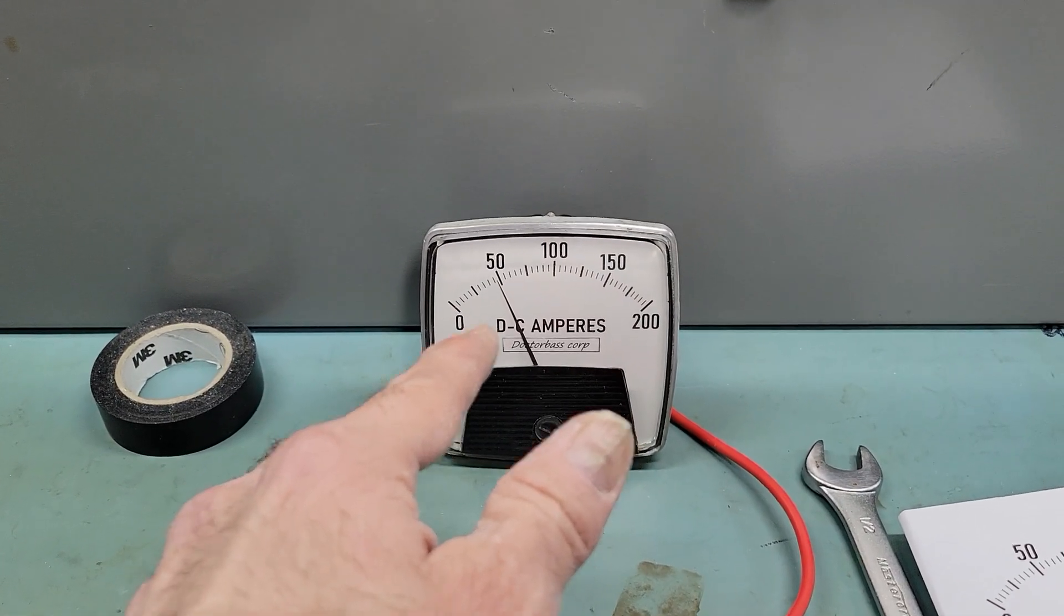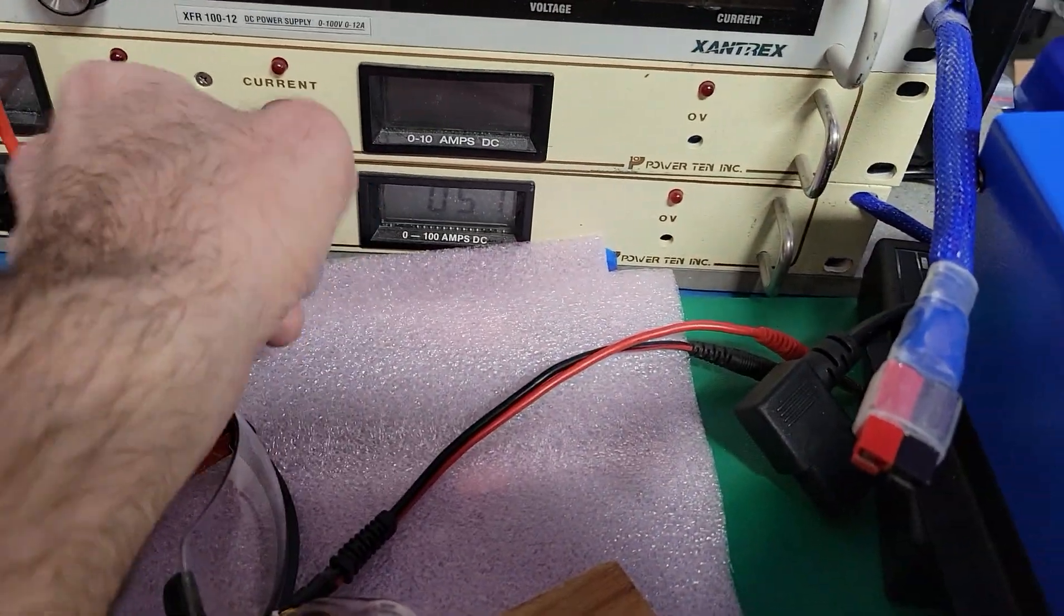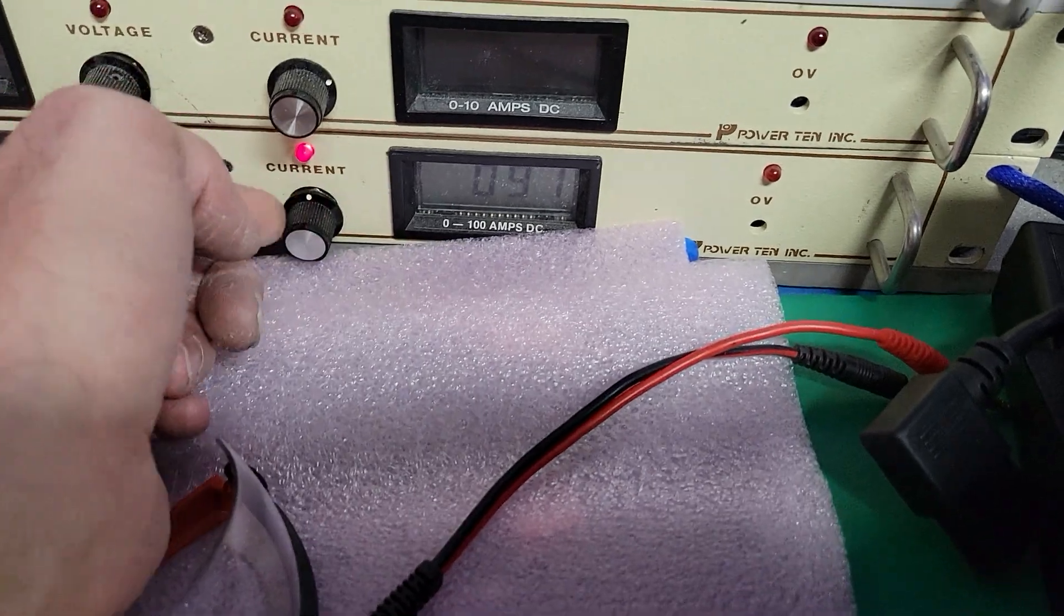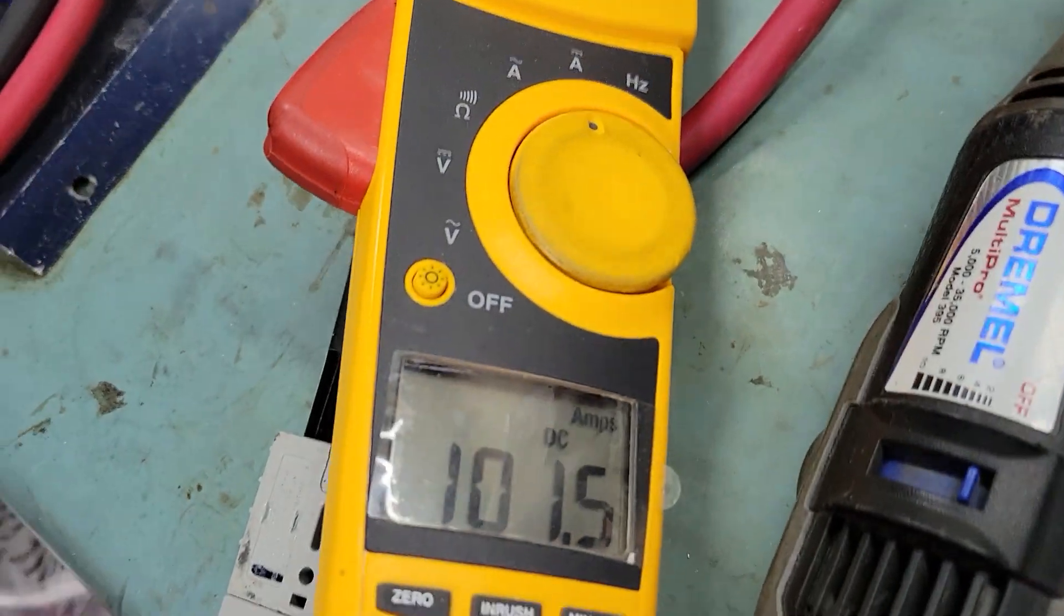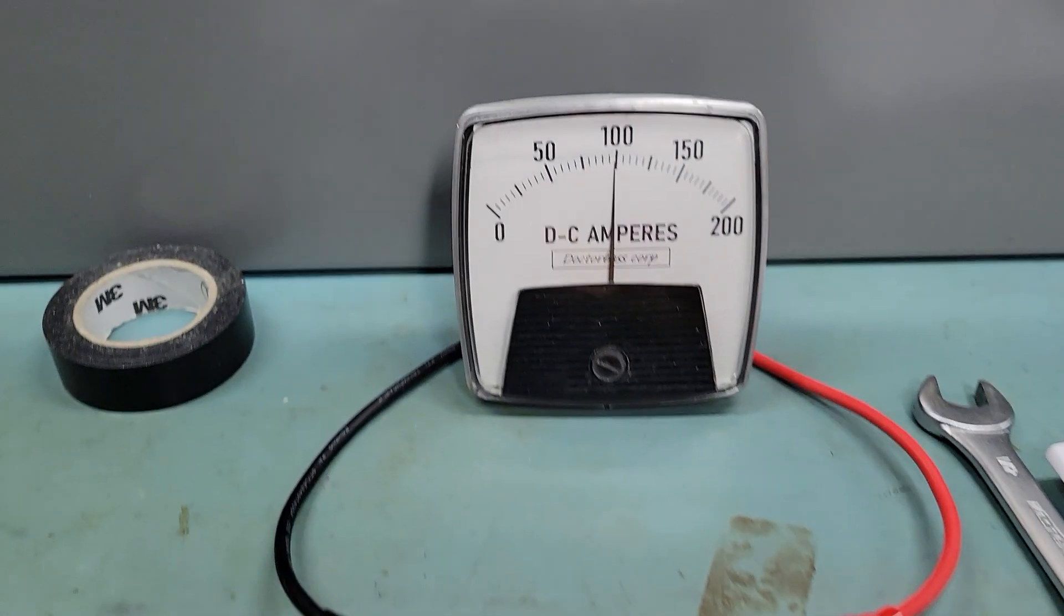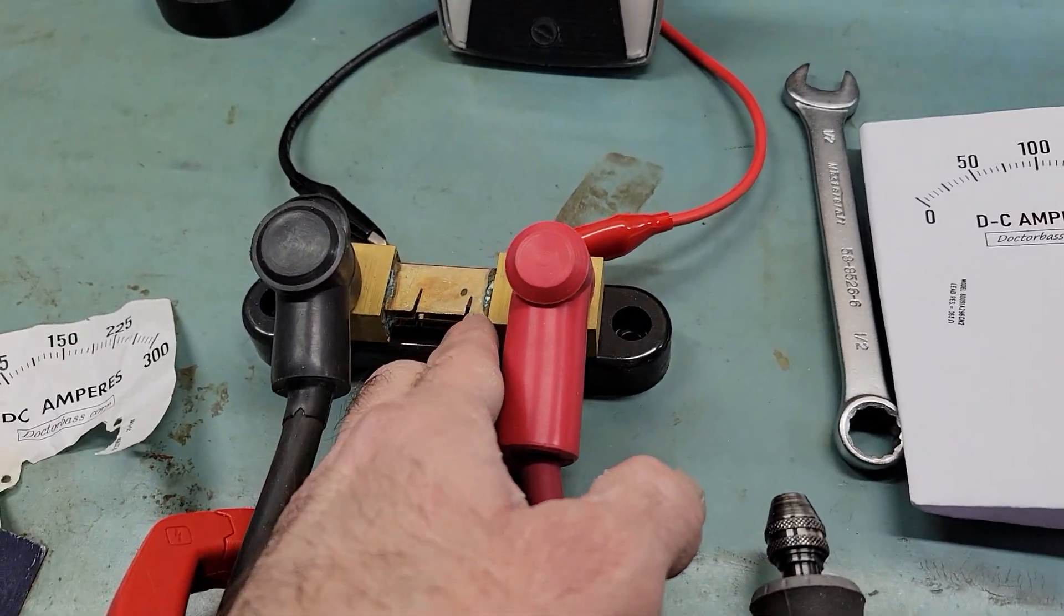If I go to 100 amps here, 99, 100, very close. You will see I have 101, and you see we're pretty close. I could just grind it a little bit more in order to get the right voltage drop and have the meter to display the proper value.